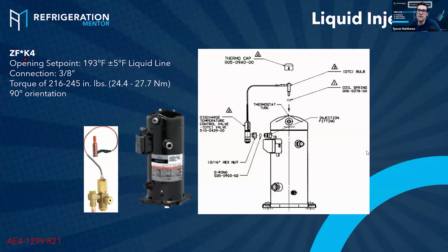And so this one here, the ZF K4, is 193 Fahrenheit injection. 193 is what in Celsius? About 90 degrees Celsius in injection. But there's other ones that are 250 Fahrenheit, which is about 121 Celsius, that will do the injection. Bitzer does discharge superheat. Copeland doesn't. So Copeland just wants you to go and check what's that discharge temperature. They want to keep it below a certain temperature. Does anybody know what that temperature should be? They want you to keep it below.